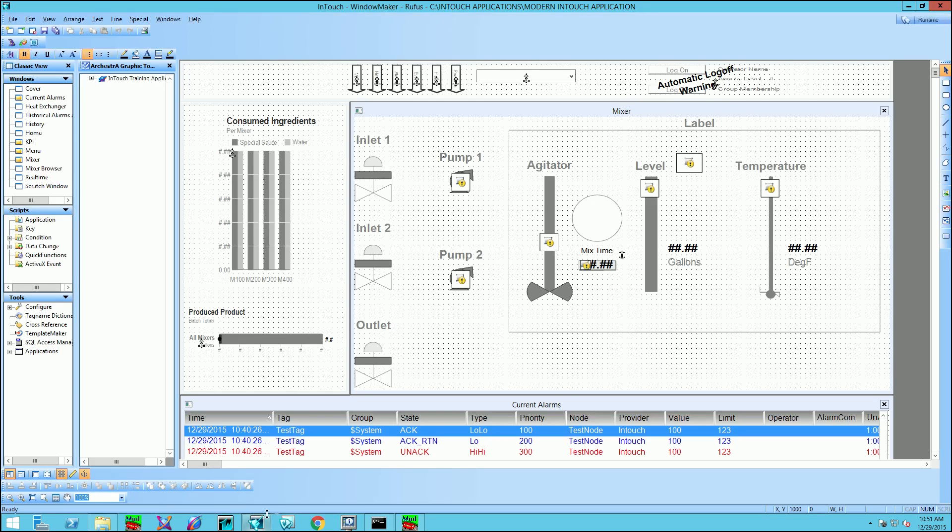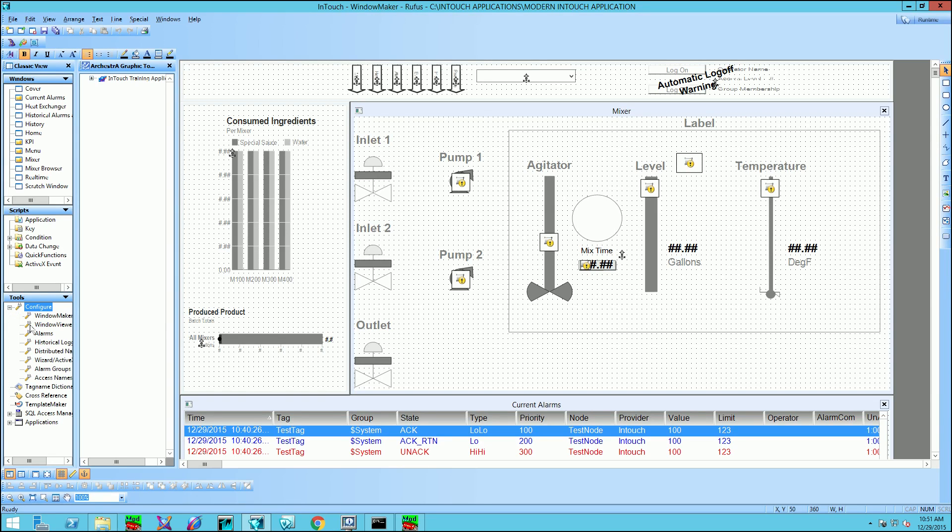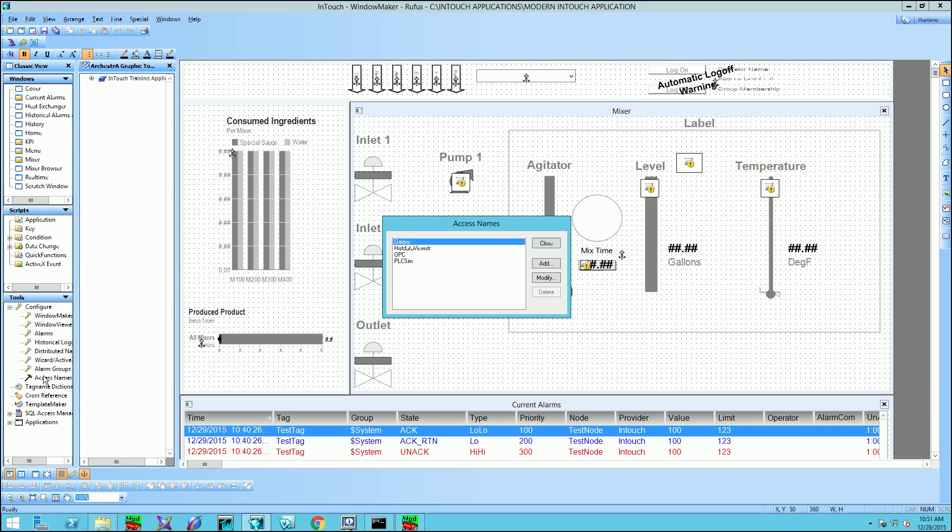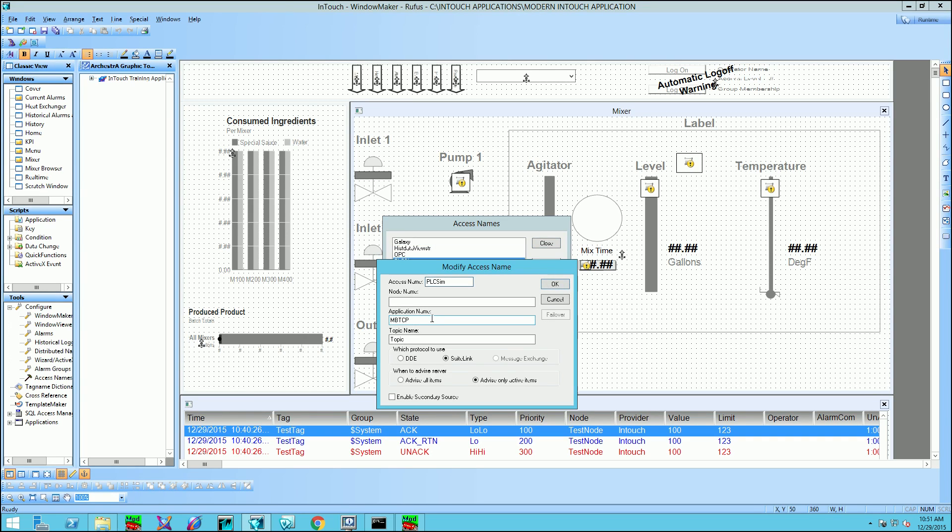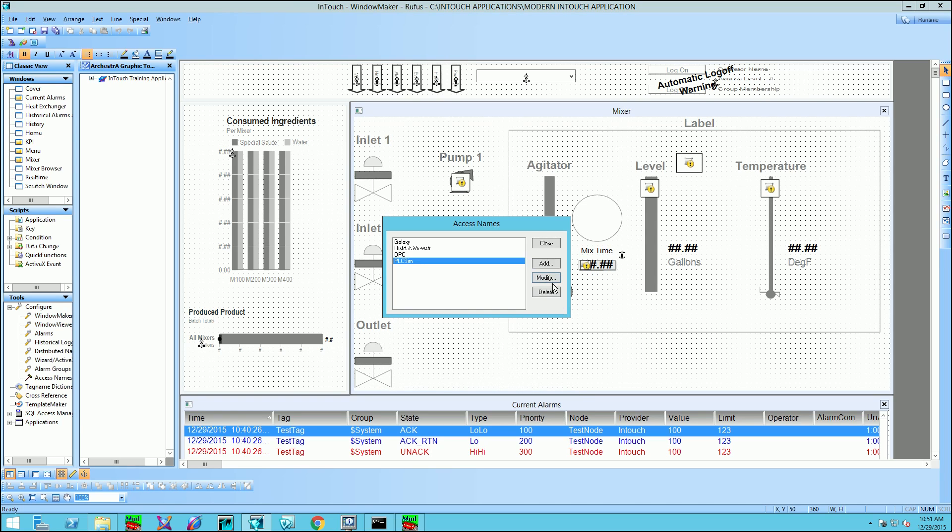Now, back at the master node, I'm going to open up WindowMaker. And what I'm going to do is I'm going to configure the access name to reflect the new DA server that's on the remote node. So I'll just select Modify. And as opposed to MBTCP, I'm going to say DAS MBTCP. And click OK. And then close.